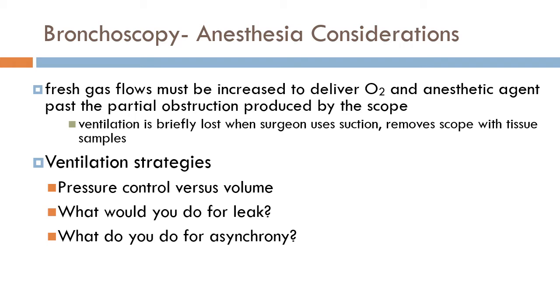So it's going to automatically adjust. It does it for us because all it cares about is you told it to do a pressure of 10. It's going to have a hard time to get to pressure of 10. Therefore, it's going to throw more volume. It's going to turn your highway to the lungs from a 2-lane to a 4-lane to try and achieve that pressure that you set. So it helps overcome the loss and having a hole in the airway, which is the three-way port. Does that make sense?